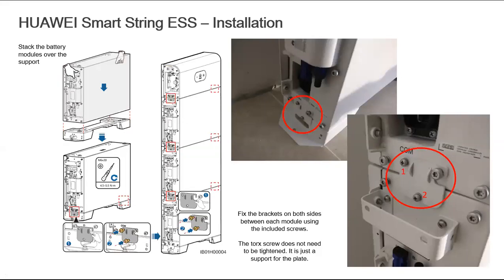Coming back to the installation of the battery, you can see on the left side of the screen the floor base module. You can stack the battery onto that floor base, and then put all the battery modules up to the top, where you will install the power control module. Also, you will find the expansion module plates in the battery, which are very necessary to lock the power control module to the modules.